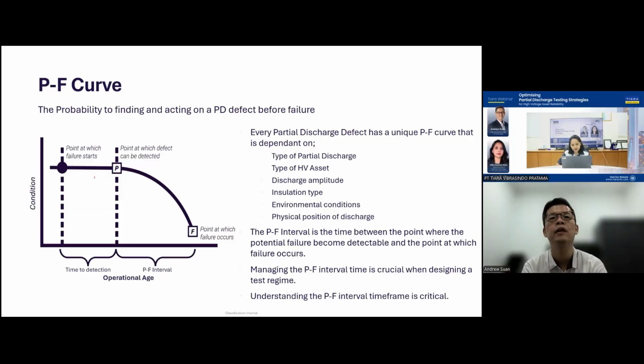Then sometimes you also want to know the location where your substation is built. Some substations may be built near a river. If near the river, then of course the humidity will be much higher, and you are more prone to surface discharge. Some are high up in the mountains. In the mountains, the temperature change is very drastic. Sometimes the daytime is very hot, but at night it becomes very cold, and then you start to have condensation. So these are certain things you also want to take into consideration.